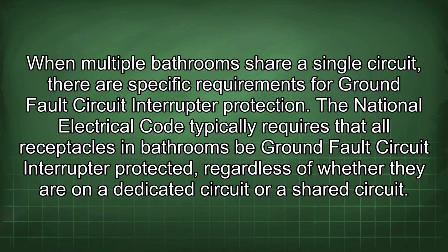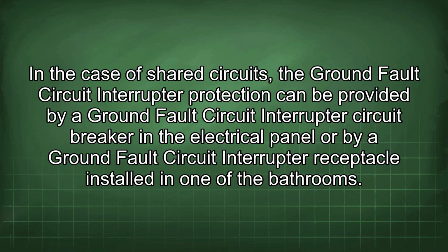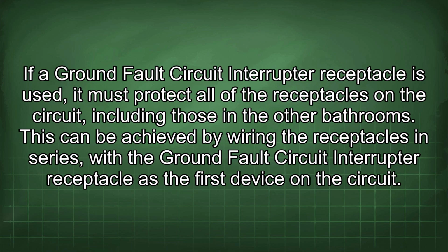When multiple bathrooms share a single circuit, there are specific requirements for ground fault circuit interrupter protection. The National Electrical Code typically requires that all receptacles in bathrooms be ground fault circuit interrupter protected, regardless of whether they are on a dedicated circuit or a shared circuit. In the case of shared circuits, the ground fault circuit interrupter protection can be provided by a ground fault circuit interrupter circuit breaker in the electrical panel or by a ground fault circuit interrupter receptacle installed in one of the bathrooms. If a ground fault circuit interrupter receptacle is used, it must protect all of the receptacles on the circuit, including those in the other bathrooms.